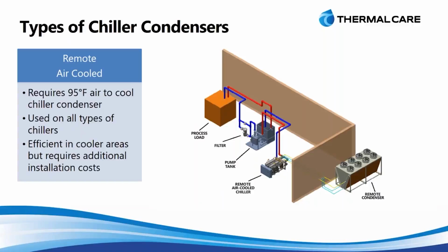The next step would be a remote air-cooled unit. And with the remote air-cooled unit, we've essentially taken the chiller and we've separated it into two pieces. We have the condenser and then the chiller itself, where it has the compressor. What we're showing here is a remote air-cooled unit, and the condenser is located outside. It still has the fans. It still has that air to refrigerant heat exchanger using forced air to cool. So very exact same concept as the integral unit. We've just separated them into two.